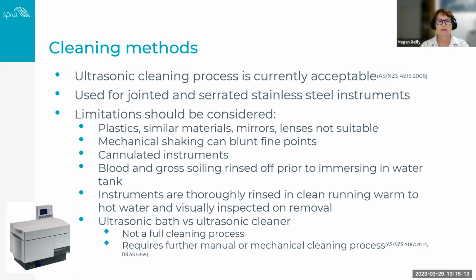We clean the ultrasonic, and we refill it and degas it, and then for the next lot of instruments that are going in. So this is really why 4187 currently, and the new draft standard, actually states that if you're using an ultrasonic cleaner, then further manual cleaning or a mechanical cleaning process such as a washer disinfector is actually required. So ultrasonic, in those standards, is actually seen as a pre-cleaning.